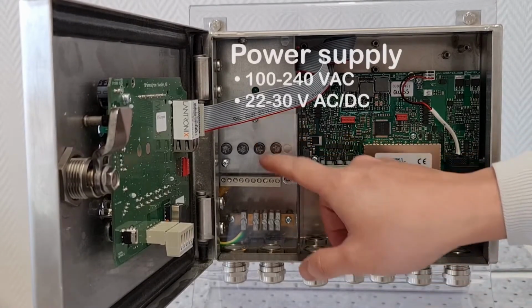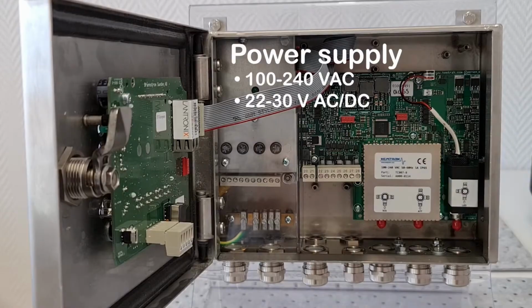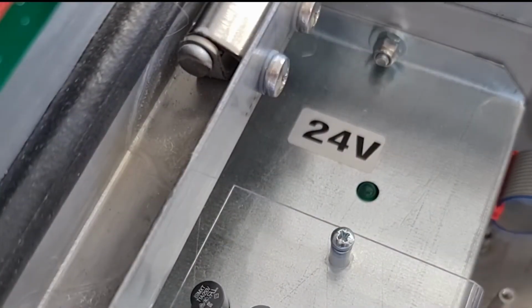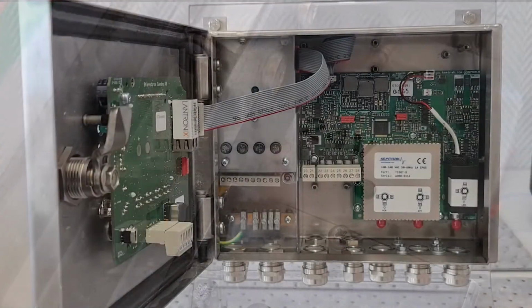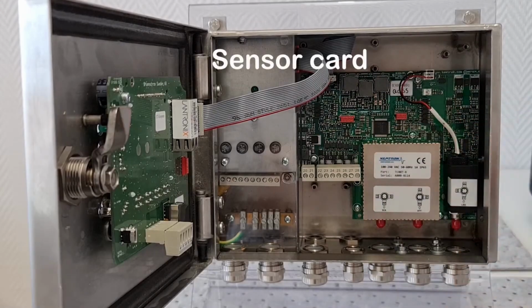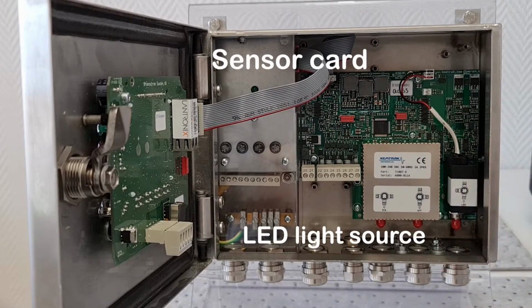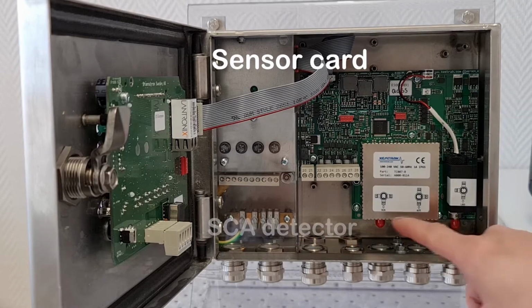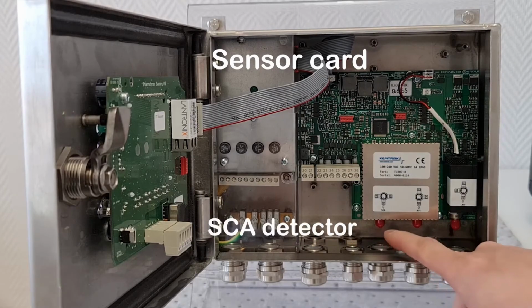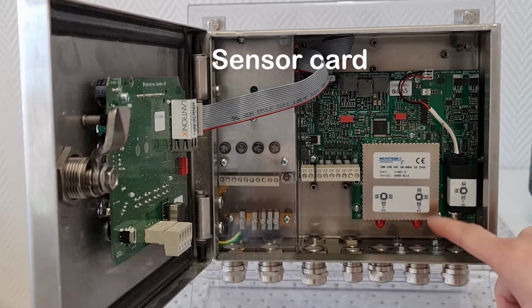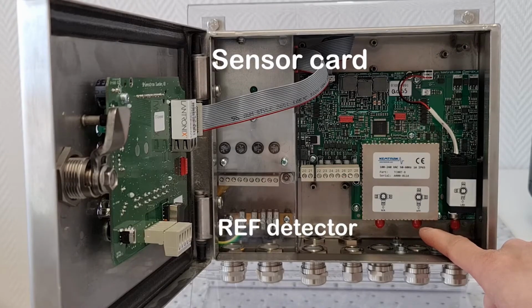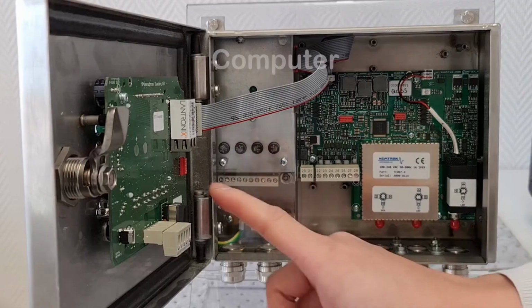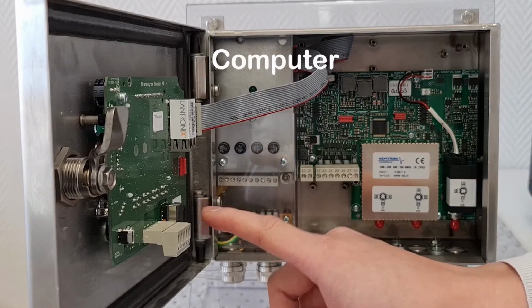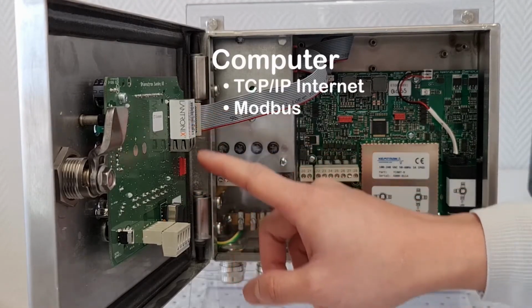The power supply unit is located on the left side and is available in two models. The sensor card is what performs the optical measurements. The high-performance LED light source is located to the right. There is one photodiode detector monitoring scattered light, and a second reference detector that monitors attenuated light. The computer is mounted on the front door of the analyzer. The Internet and Modbus connector is also located here.